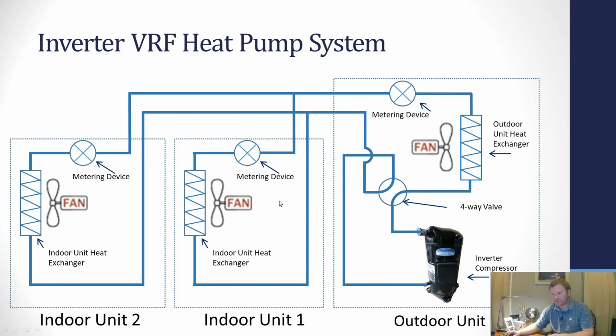A quick example, on a VRF system, if unit 1 is in auto, then unit 2 follows whatever mode the system is in, because indoor unit 1 is the one that's in auto. It's the master. If indoor unit 2 has a set point of 70 degrees and the room temperature is, say, 72 degrees, while the system's in heat, it's thermo off, fans off. It's not going to heat because the room is already warmer than the set point. If indoor unit 1 switches to cooling, well, then indoor unit 2 will go ahead and cool down to 70 degrees and then satisfy again. So it pretty much just always turns the fan off if it's past the set point, so you're never drifting too far from whatever your comfort level is. It's a simple way of putting it. Again, we'll talk about this in more detail at a later date.